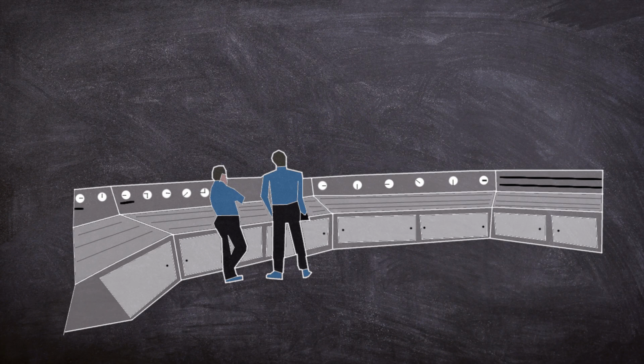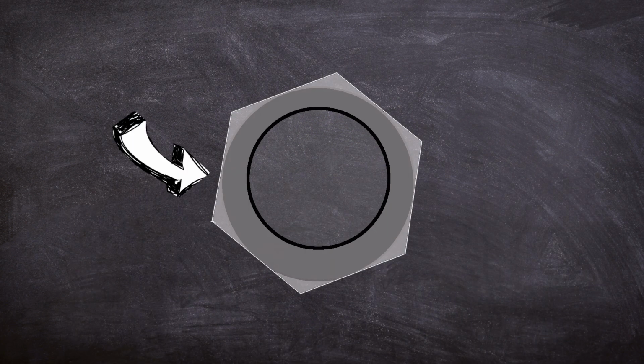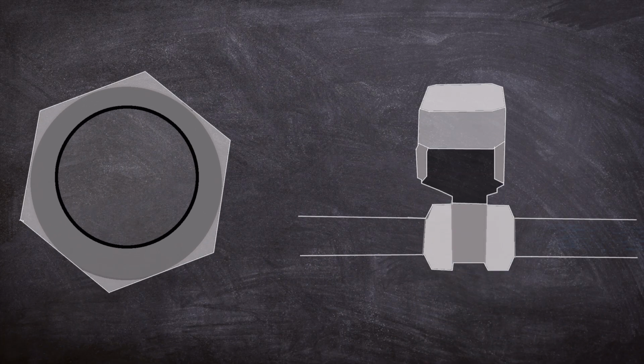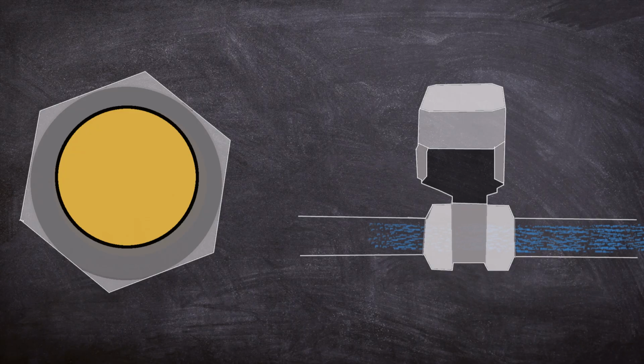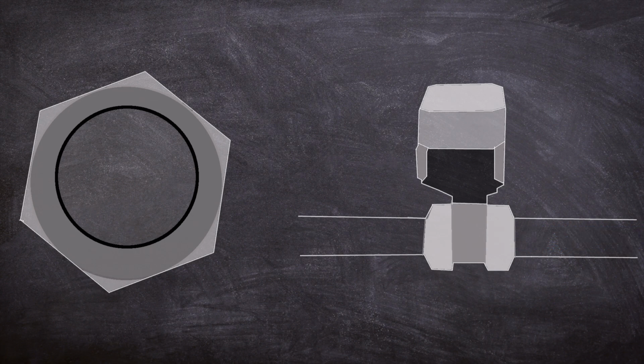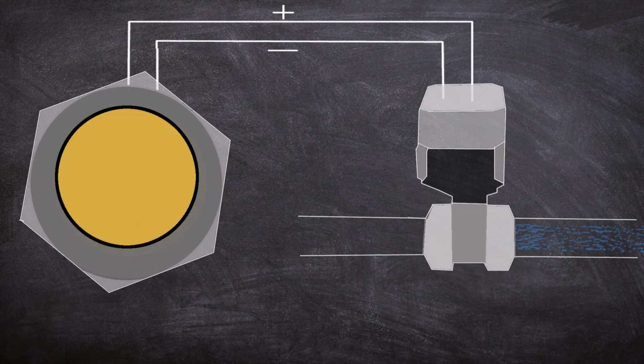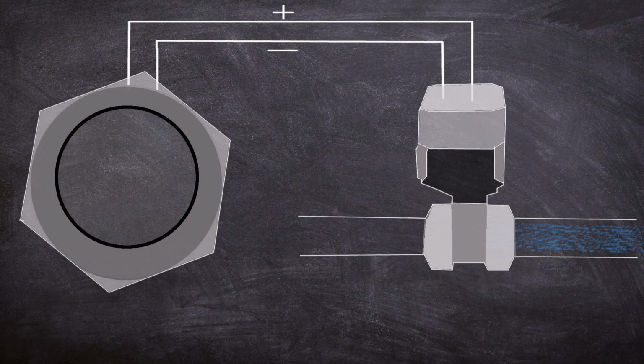The control room had some confusing design quirks, one of which being the indicator light for the pilot-operated valve, the one stuck open allowing coolant to escape. A light was provided to signify the status of the relief valve. Light on means open, light off means closed. Well, that wasn't the case. The operators weren't aware that the light only signifies the state of the electronic solenoid, as the bulb was wired to the circuit. When the valve was working correctly, the light bulb would give an indication as lack of power to the solenoid, reverting the valve to a closed state, and the operators had been conditioned to think light off, valve closed. However, this morning the valve had a mechanical issue, meaning it was stuck open, but power had been cut to the solenoid, extinguishing the indicator bulb, giving an assumed closed valve state to the operators.